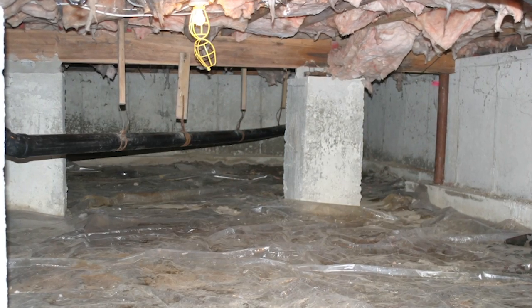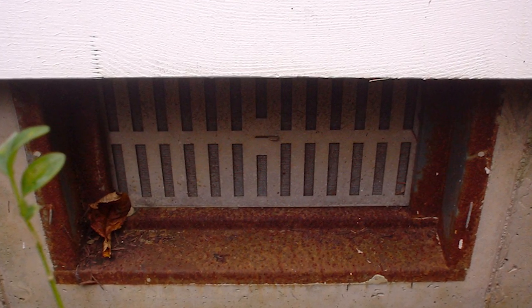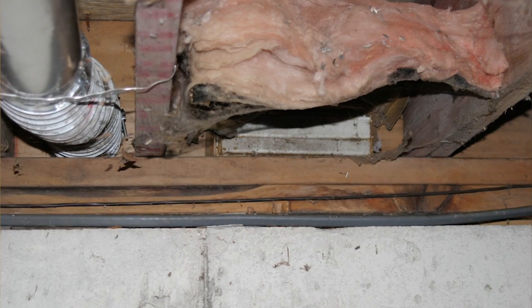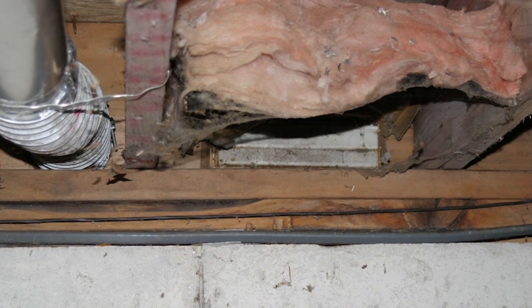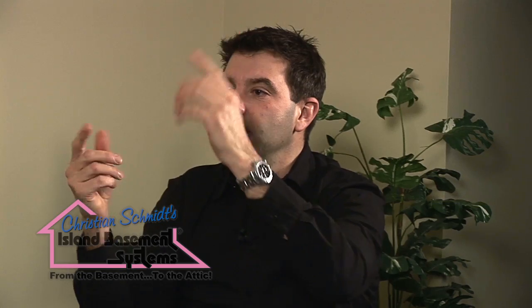That's why in the summertime we're actually moisture loading, and that's why we have so many complaints of musty smelling crawl spaces. In the wintertime, those vents let cold air in — even ones with a little slider to close still get cold air through. That cold air works its way right through the batt insulation, floors get cold, and then the homeowner turns up the heat, which creates more heat upstairs that rises faster and pulls in even more cold air into the crawl space. Vented crawl spaces to the outside is just a dumb idea.